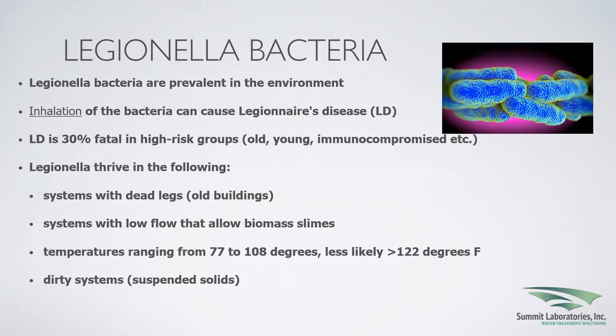With this low flow that we're seeing, we see the domestic hot water loops set to cool off because we don't have the flow, dropping below that 120 degrees mark. And then in dirty systems, so along with, you know, your old systems or low flow scenarios, allowing those suspended solids to fall out and sit in the bottom of the pipe.